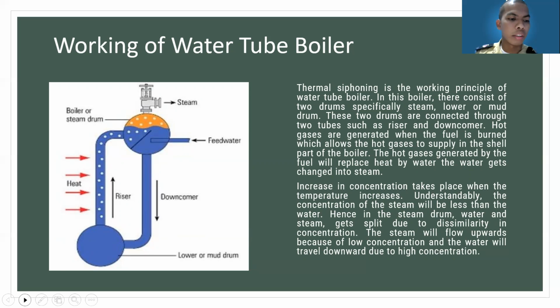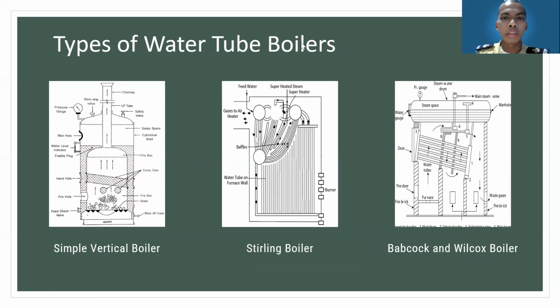Okay, next. These are the types of water tube boilers. There are basically three types of water tube boilers. The first is the simple vertical boiler. A simple vertical boiler is a type of boiler which generates steam at low pressure and in small quantities. It produces a pressure of almost 10 bar. Out of all the boilers, its construction is simple and straightforward.